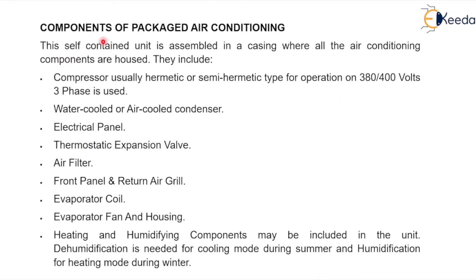In a packaged air conditioning unit, the following components are present: compressor (three-phase), water-cooled or air-cooled condenser, electrical panel, thermostatic expansion valve, air filter, front panel and return air grill, evaporator coil, and evaporator fan and housing. Heating and humidifying components may also be included. Dehumidification is needed during summer and humidification for heating during winter.